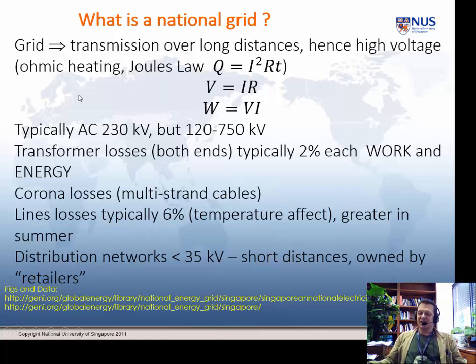Now, remember ohmic heating, Joule's law, where the amount of heat generated, Q, is proportional to the current squared. That's why when you're looking at transmission over long distances, you do not want a lot of current, because that's going to heat your conductors, which is going to reduce their efficiency or increase their resistance. So typically in the grid systems, you might have 230,000 volts up to 750,000 volts. The issues here are quite significant. They're climate related. So in climates where you get cold winters, the same type of conductor can carry more energy than maybe in Singapore, where everything gets hot. If you put cables underground, they're cooler. You can usually carry more power.